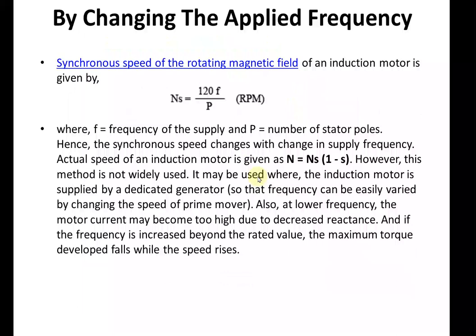In order to prevent these problems, we go to the next method — changing the applied frequency. The formula is: synchronous speed Ns = 120f / P, in rpm. So frequency is directly proportional to the synchronous speed. By changing the frequency we can change the synchronous speed, where P is the number of stator poles. The actual speed of the rotor is given as N = Ns × (1 − slip).